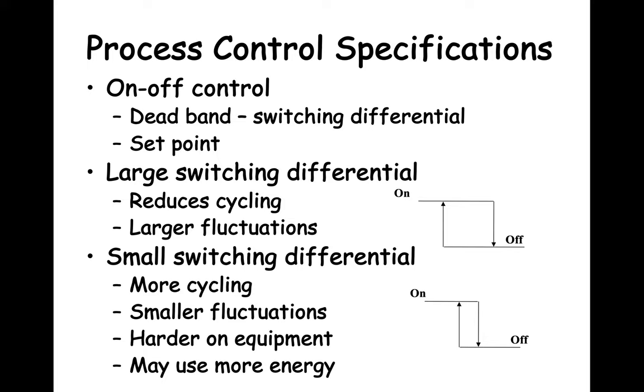Many processes use on-off control, where the user sets the setpoint and the switching differential, and the controlled equipment is either fully on or fully off. If you choose to use a large switching differential, you will have less cycling, but you will have larger fluctuations in the process output value. If you choose to use a small switching differential, the equipment will cycle on and off more often, but the process output will not fluctuate as much. Excess cycling can be hard on equipment as it goes from off to on.